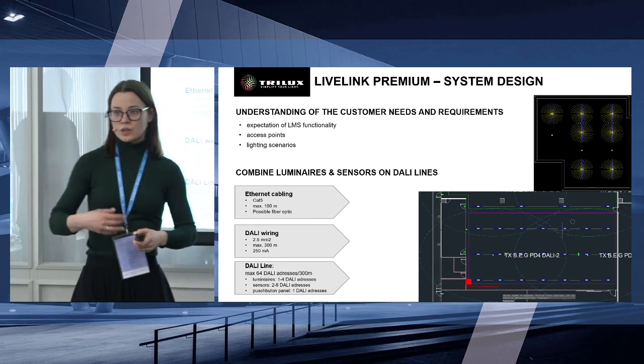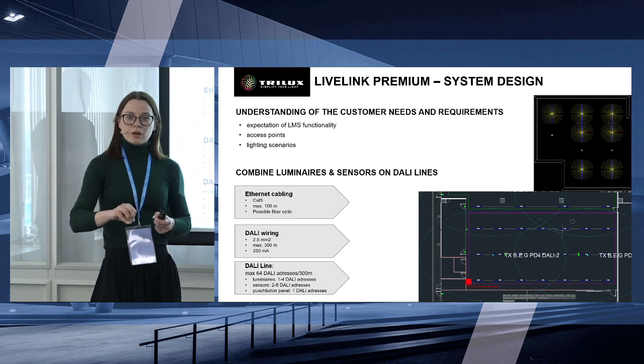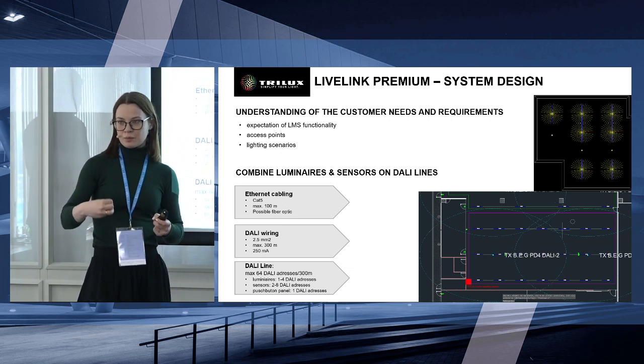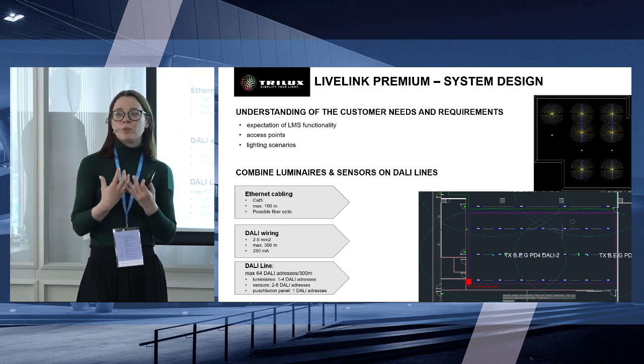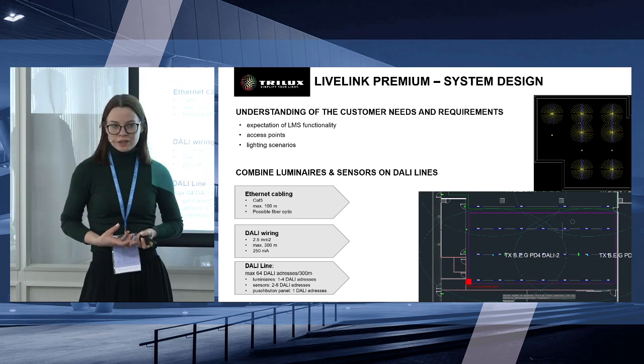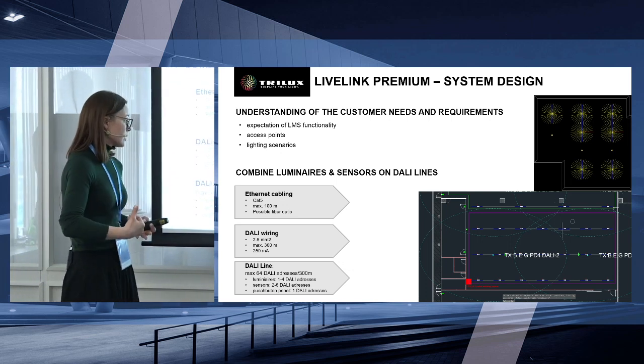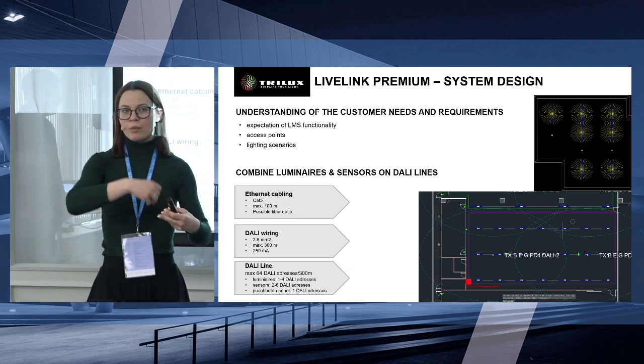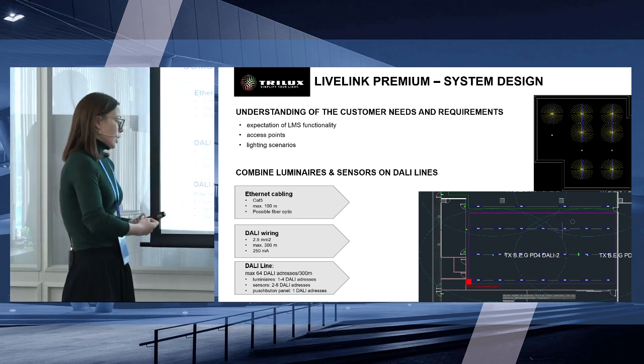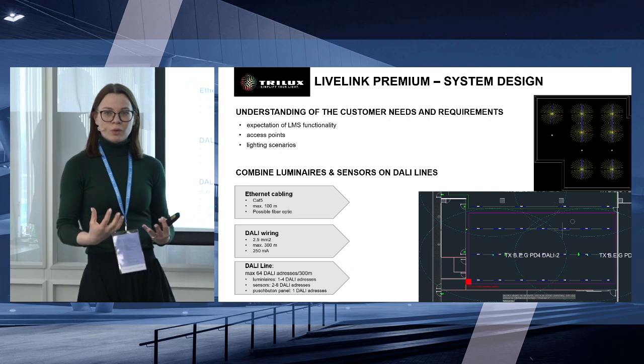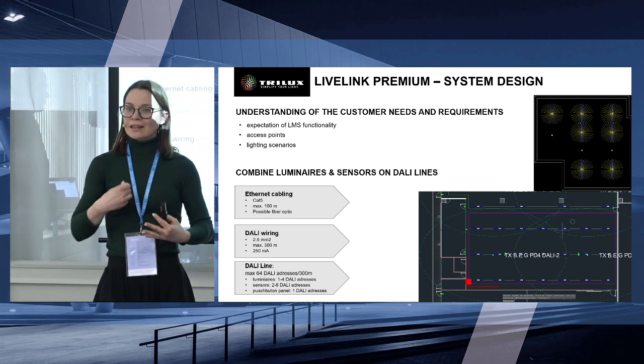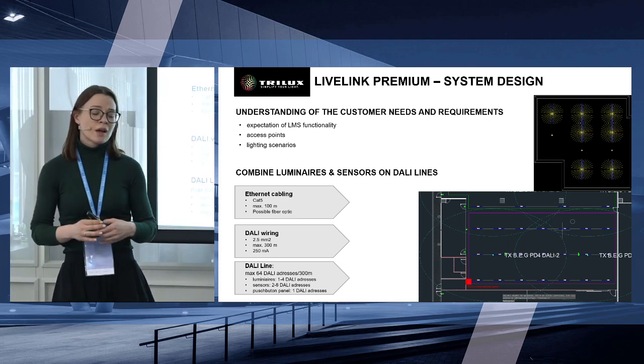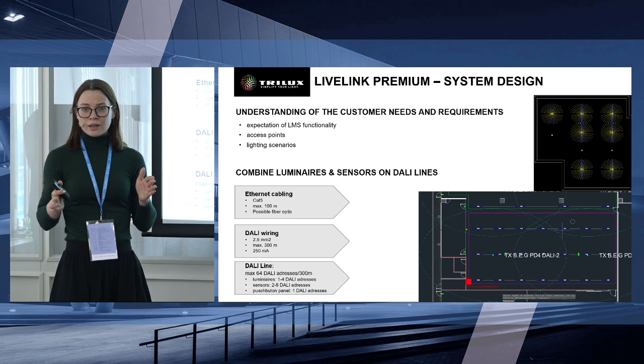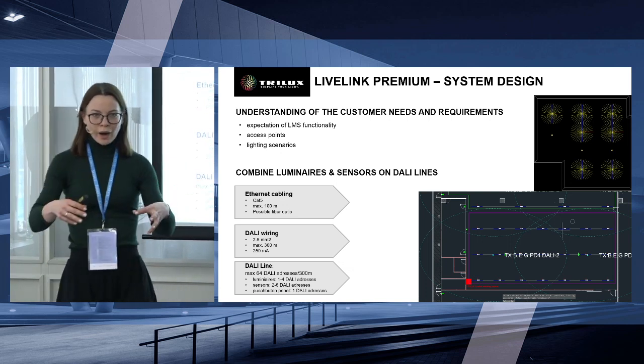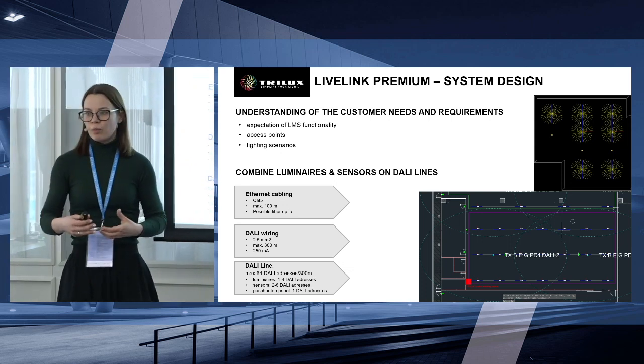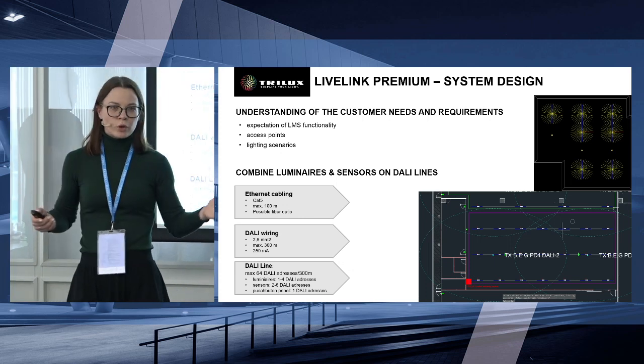When we want to give our customer a light management system, we have to remember that luminaires have to be prepared for this, and we need luminaires with a DALI driver, and all our luminaires have to be connected by DALI wiring. In one DALI line, we can have 64 DALI addresses. It's important to remember that some luminaires have from 1 to 4 addresses, and it could be the same with the sensor. When we combine everything together, we have to check how many DALI addresses our product uses.